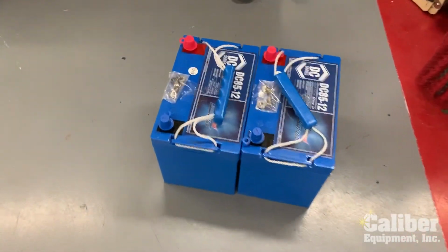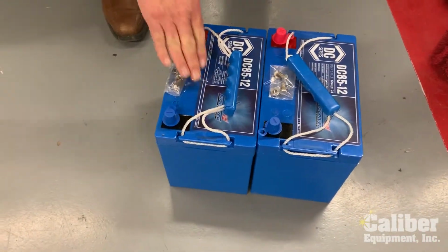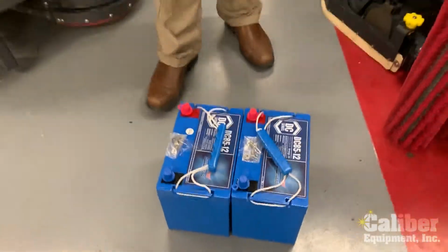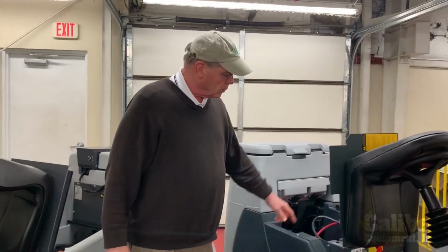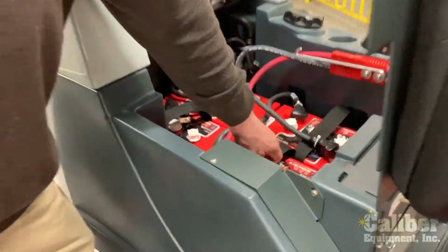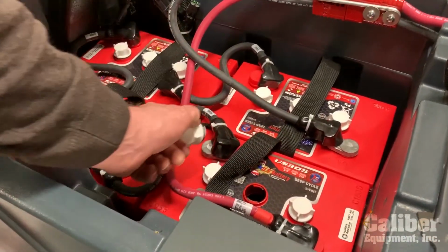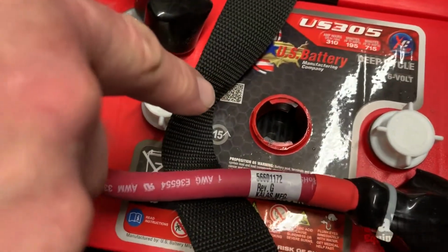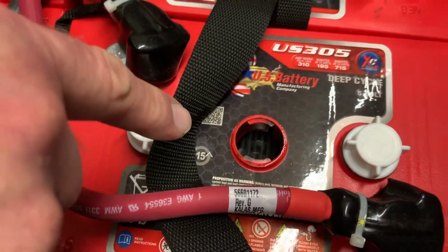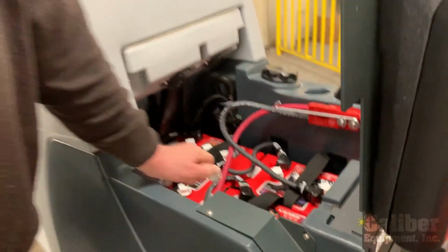Now, there's two types of batteries in the marketplace. There's lead acid and there's AGM batteries. The glass mat battery here is on the floor. You'll see that it is a sealed battery. There's no access for an operator to open up the battery and see what the condition of the electrolyte is. But if you look over here in the lead acid battery, there's actually caps. And Stephen, if you'll put that camera down where you can see the water level on these brand new batteries, it sits about a 1/4 inch above the lead plates that you can actually see.